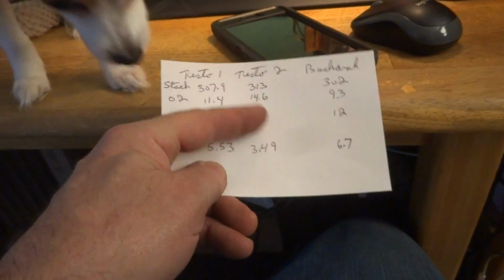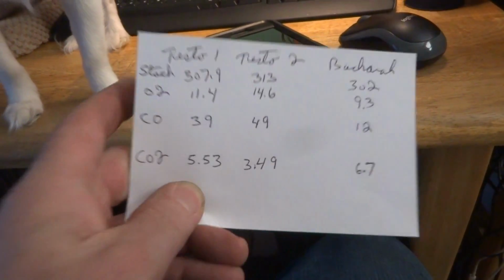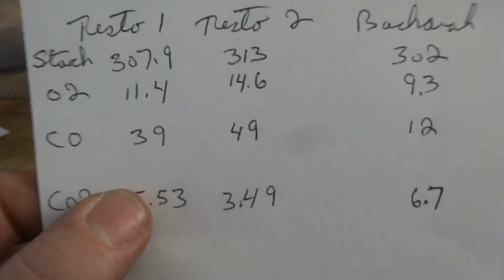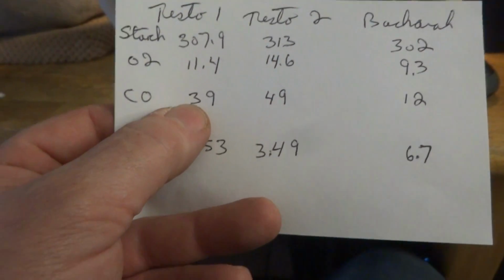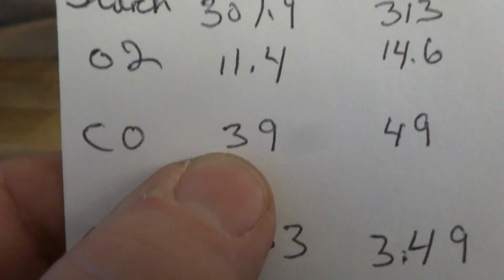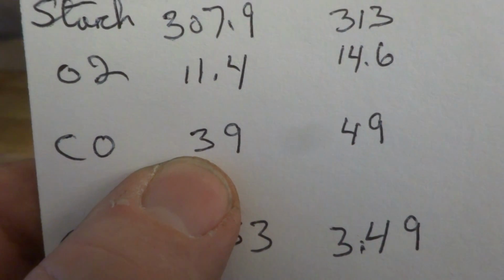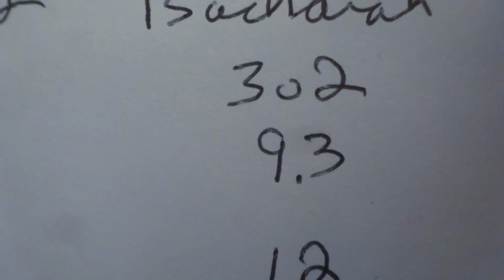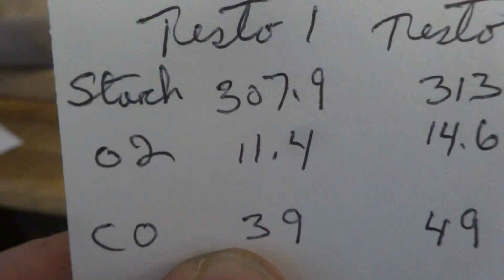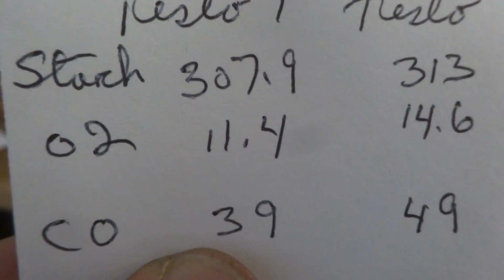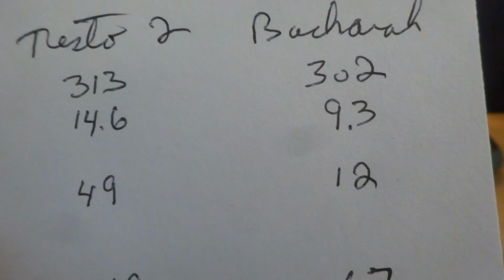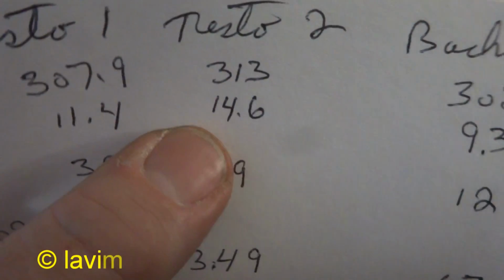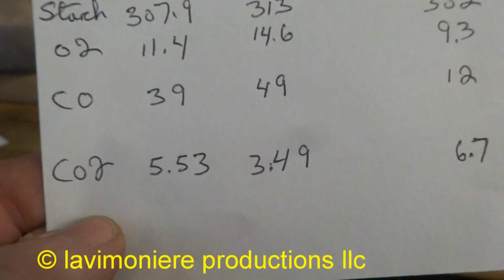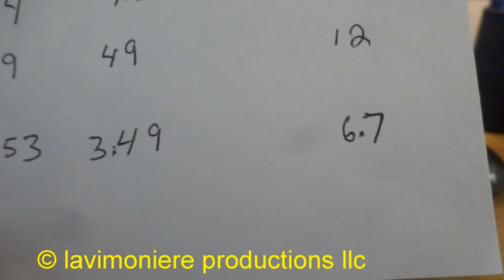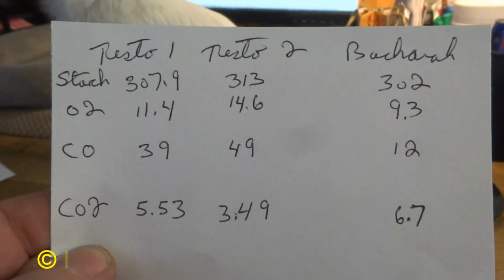You know, these two units should probably go in and have them calibrated. But I did put a new sensor in this one - the new CO sensor is brand new in this one, so I know that's not a problem. That's supposed to be factory preset. And this one's brand new - the oxygen sensor's brand new on this one, which is 9.3. And my Testo was 11.4, which isn't that far off. This one probably needs a new sensor. There it is - there's a shot right there.